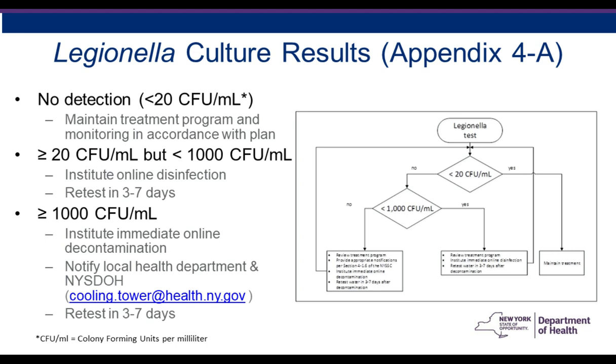Online decontamination means dosing the recirculation water with a halogen-based compound equivalent to at least 5 parts per million free residual halogen for at least 1 hour. And the cycle of disinfection, decontamination, and retesting should be repeated until the Legionella cultures return to less than 20 CFU per mil.